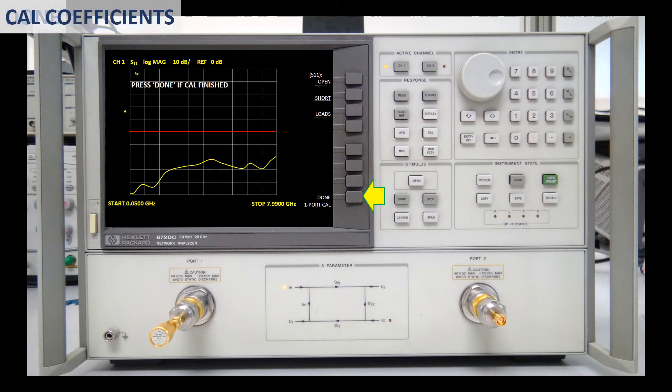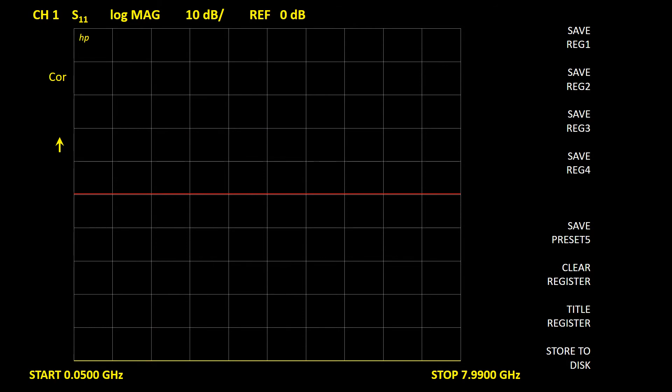Now we press Done again and the instrument starts to compute the calibration coefficients. The calibration was finished. Now the label COR is displayed at the left of the screen to indicate that we are seeing a corrected measurement.